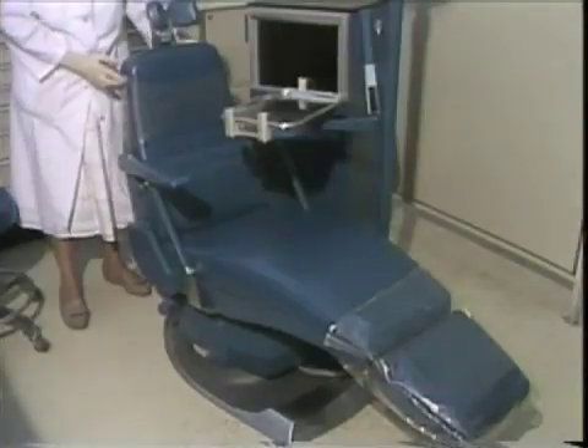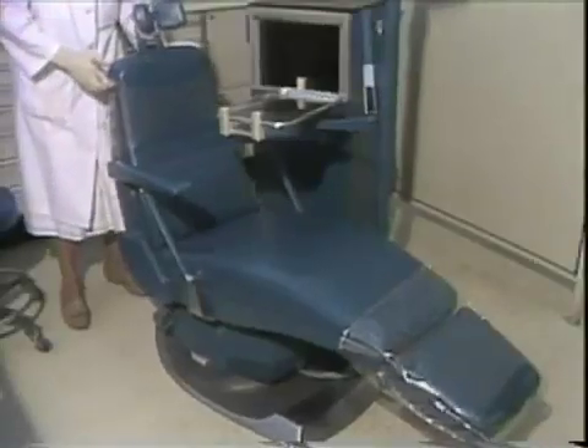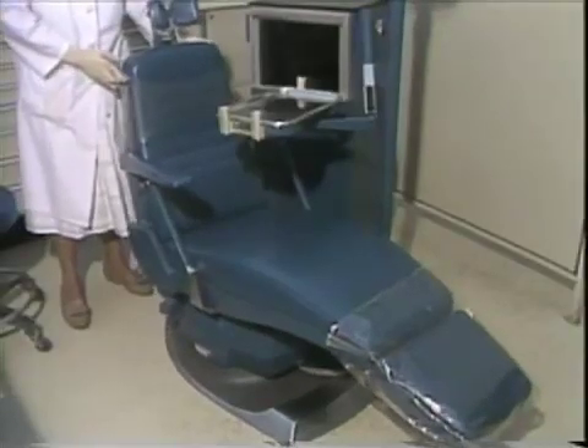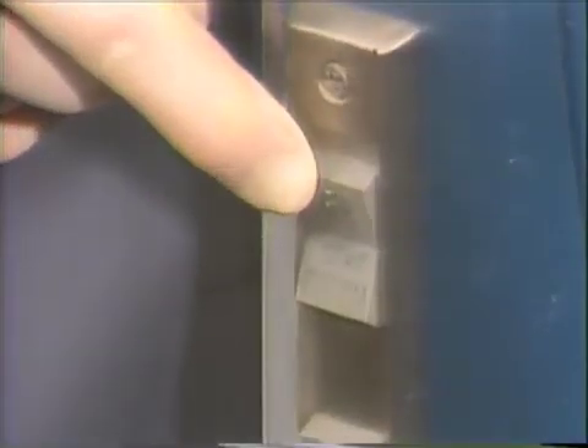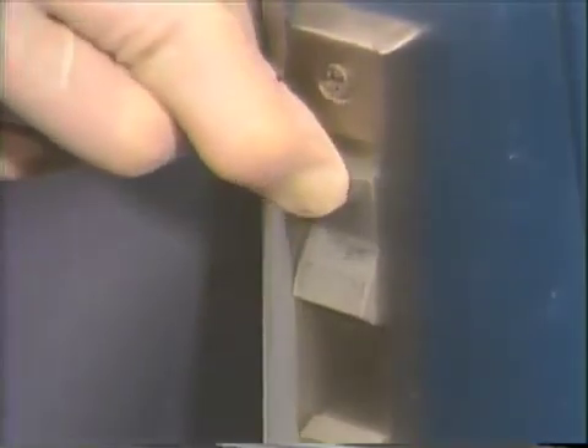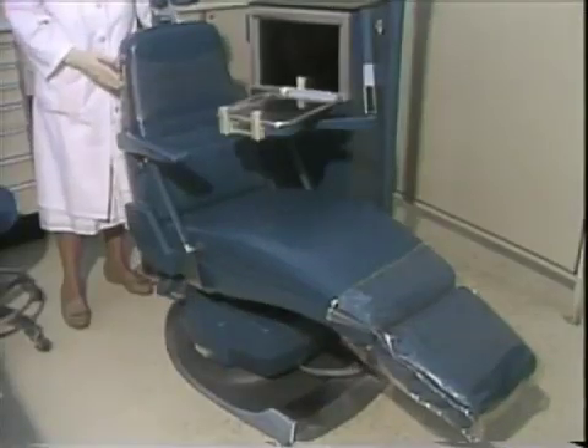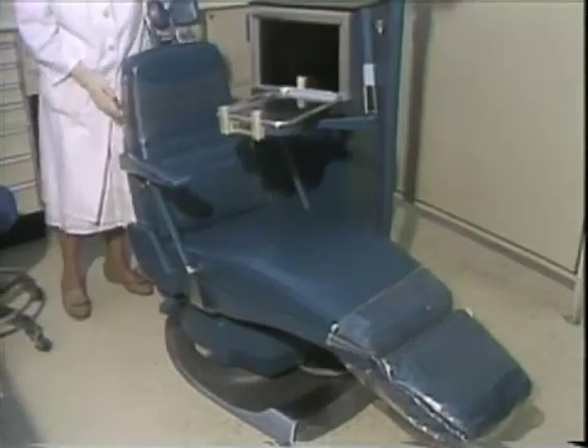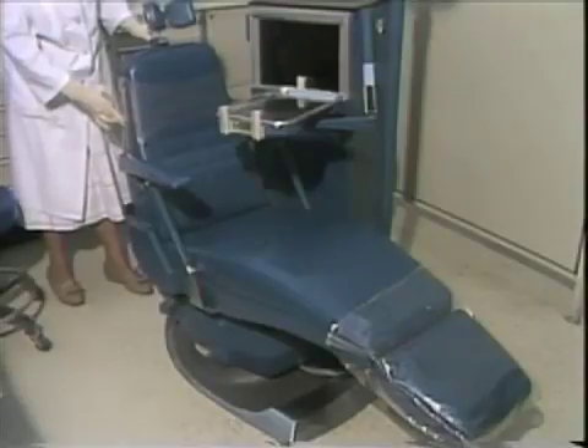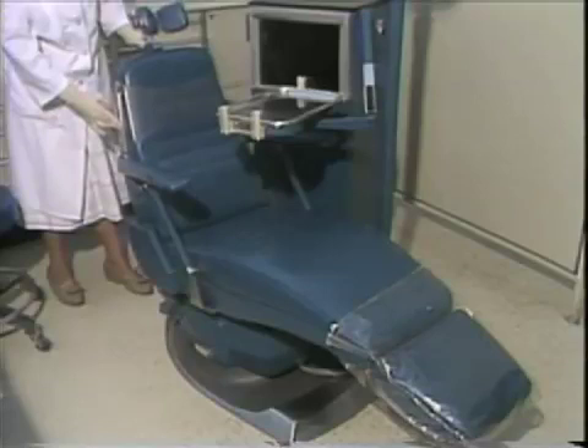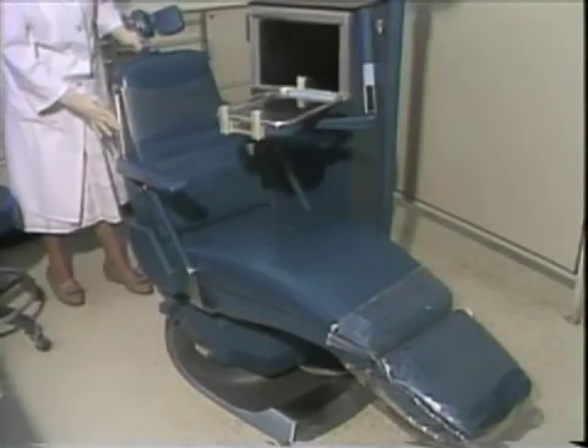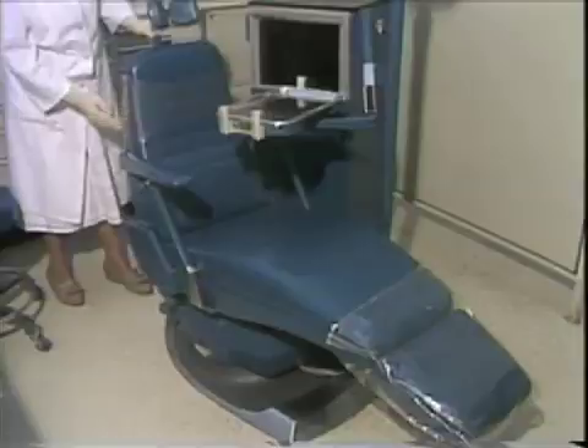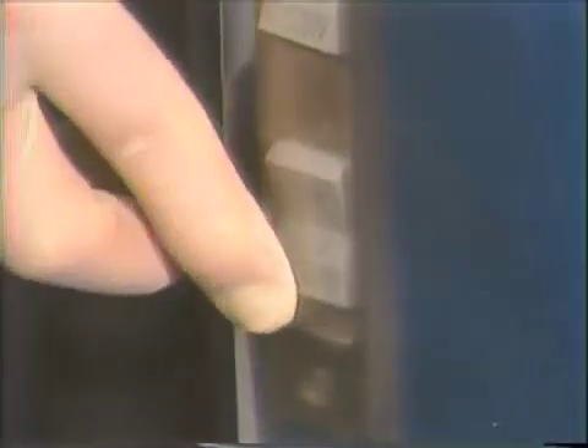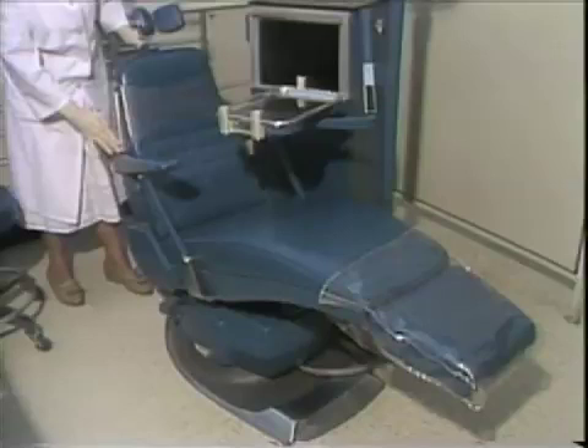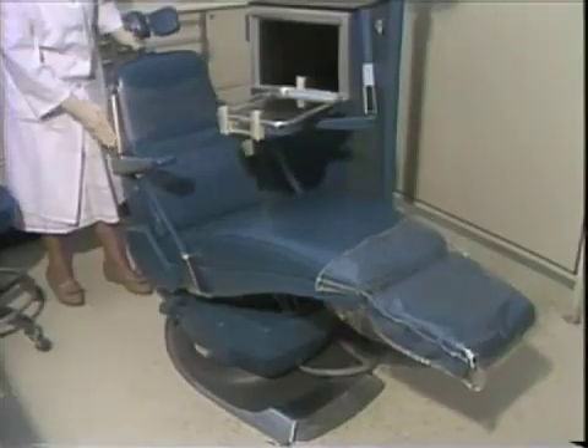The dental chair works on an air glide mechanism. You may initiate it by pushing in on the round switch. If you hear a rush of air, it is working properly. Switches for adjusting the chair include: the top switch raises and lowers the chair. The middle switch lowers and raises only the back of the chair. The lower switch tilts the entire chair. The chair should be maximally tilted when performing most dental procedures.